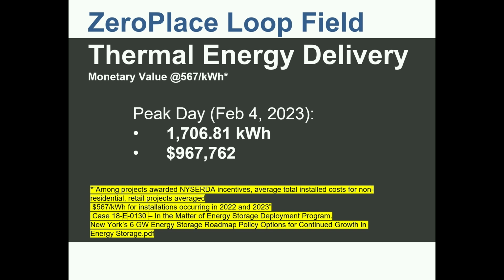And during the peak day, on this -6-degree morning, for the entire day, the loop field delivered 1,706 kilowatt hours. To create that as battery storage in the grid at today's battery prices, that saved $967,000. The loop field here was costing about $350,000. In other words, it paid for itself 3 times over in one day. That is what we have to remember. It is the biggest bang for the buck you can get.